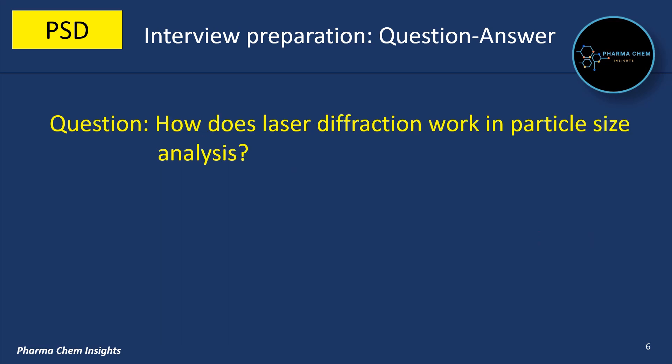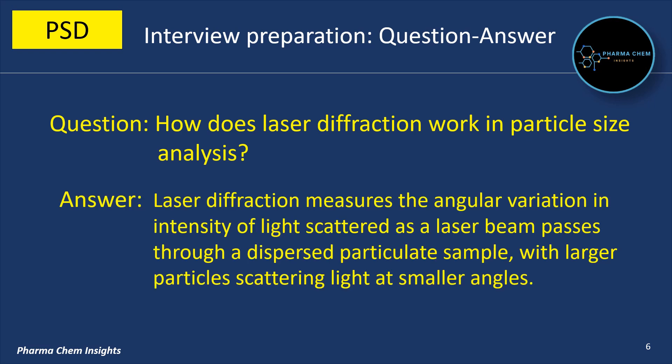Next question: how does laser diffraction work in particle size analysis? Laser diffraction measures the angular variation in intensity of light scattered as a laser beam passes through a dispersed particulate sample, with larger particles scattering light at smaller angles.